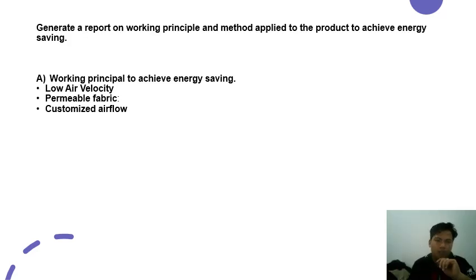The third task is to generate a report on the working principle and method applied to the product to achieve energy saving. The first one is the working principle to achieve energy saving, which is low air velocity. Fabric ducting operates at lower air velocity compared to metal ducting. Minimum static pressure needed is 20 Pascal for lightweight and 50 Pascal for medium and heavy fabric.